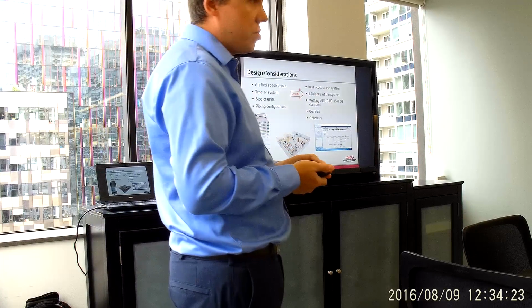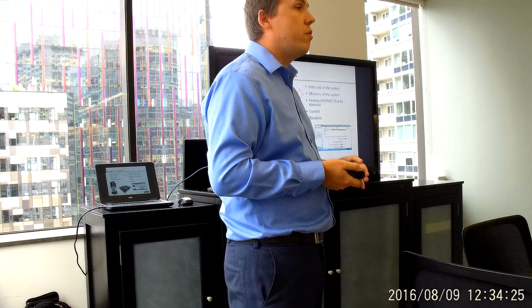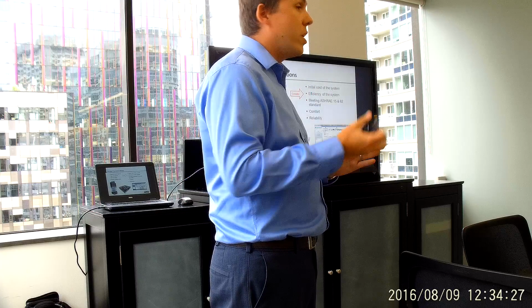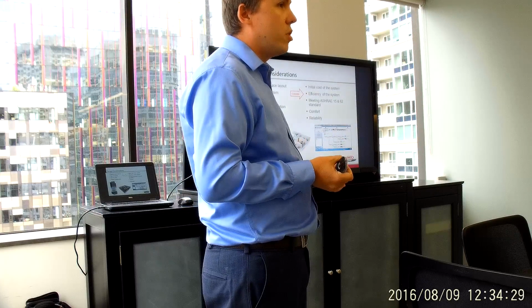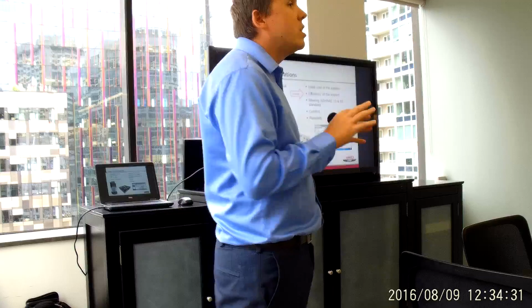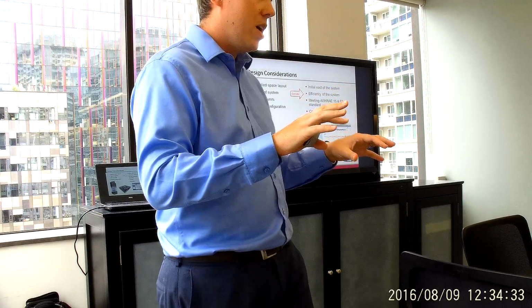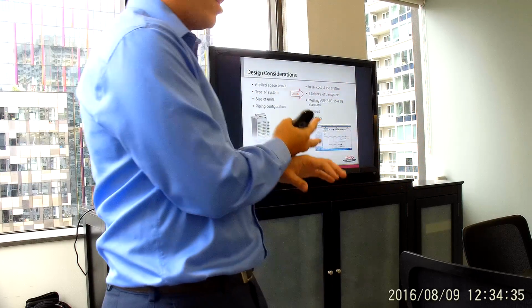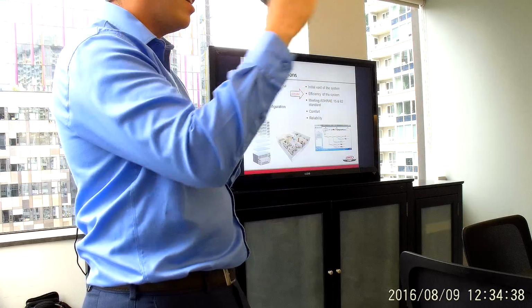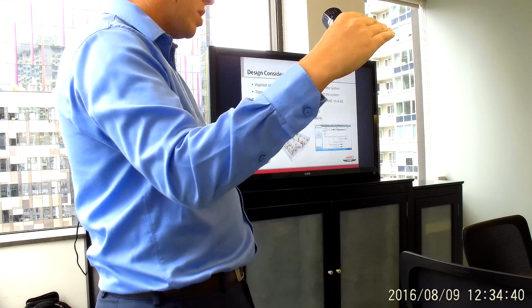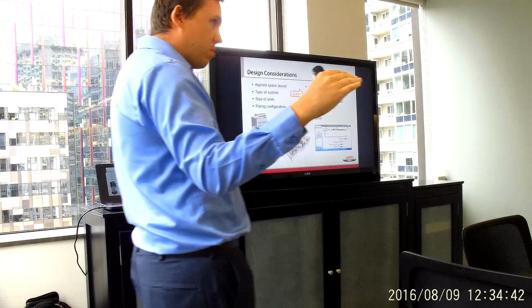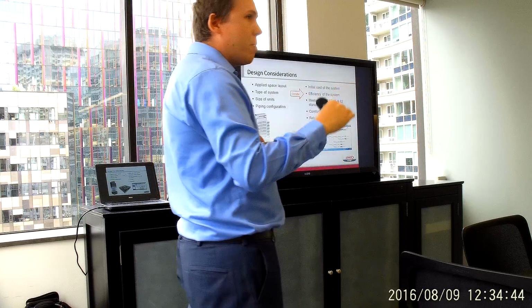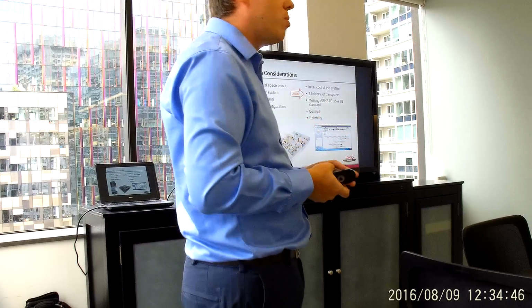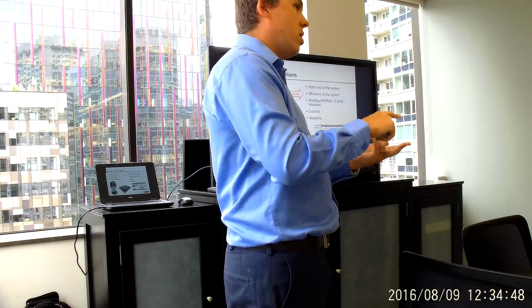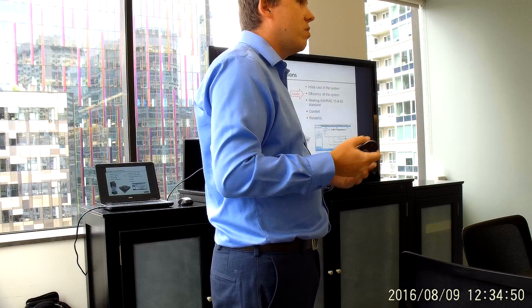I partnered with a contractor who was predominantly known for water source systems, but he had also done VRF towers. So we evaluated 10 different existing projects. I laid out the VRF for all of them, and he priced out the water source systems. So we had 10 VRF towers basically priced out, 10 water source of one type, and 10 of the other type. That's how we came to that per square footage, per door, and total percentage savings.